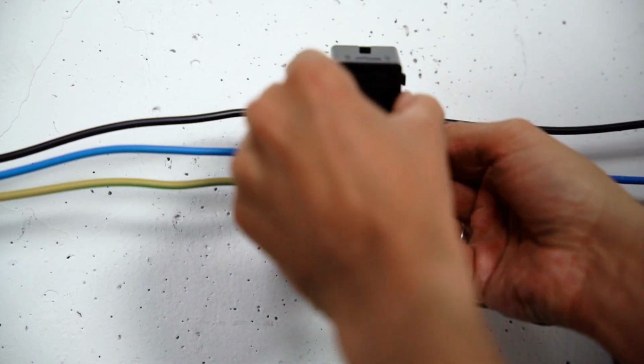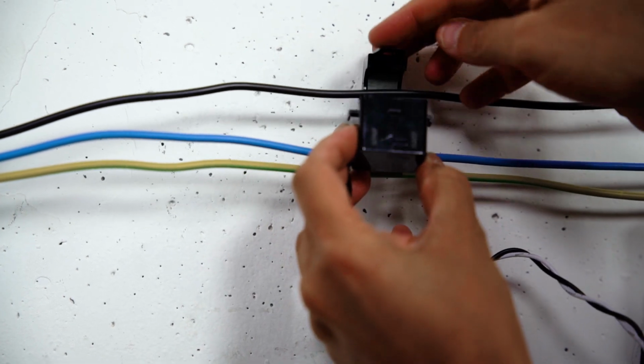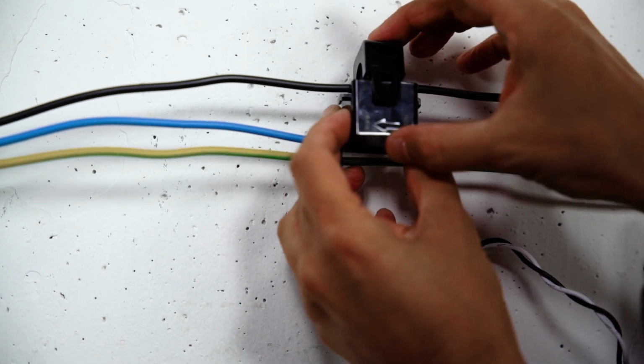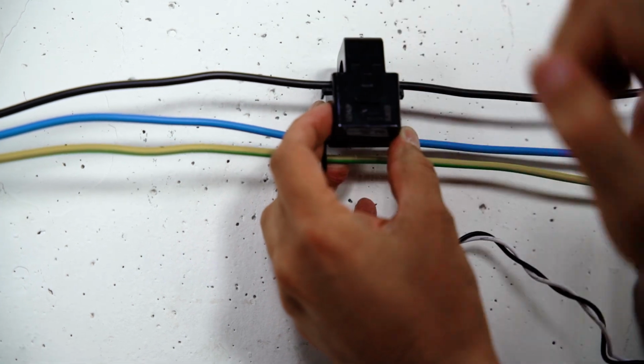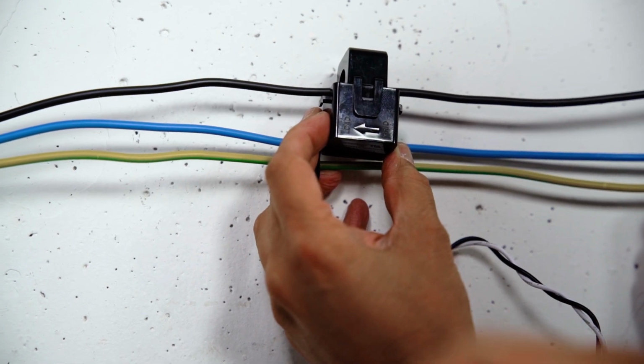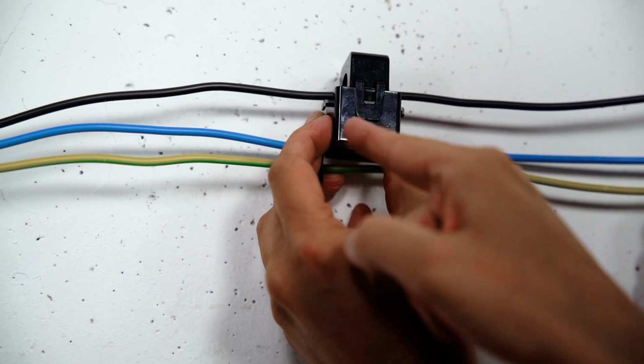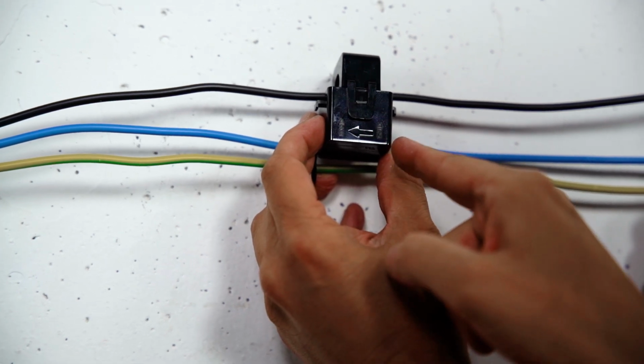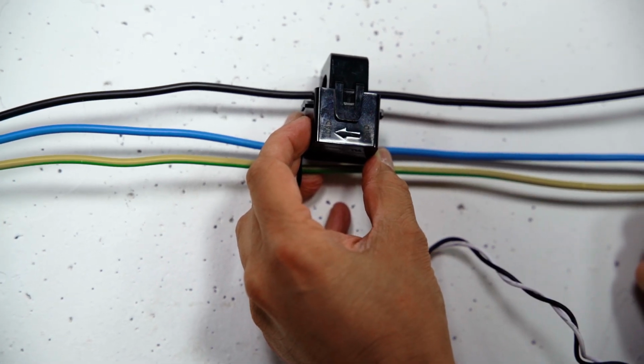It is essential that the CT is connected at the house grid connection point so that the whole house is behind the meter, including the backup load. Pay attention to the orientation when clipping the CT. The little arrow has to indicate the direction from grid to house load.